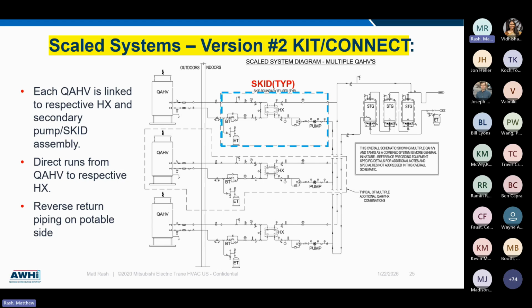It's fairly basic controls, a little DC commutated pump has its own built-in temperature controller with a temperature sensor that's wired in the field. It's all shipped loose and installed by the local contractor, but we've expanded the controls capability to allow for staging and auto rotation lead lag control. That was something that was lacking from the basic factory controls. So we've taken over that function and expanded it with a new, what we call QAHV heat tool control panel that manages all of that.